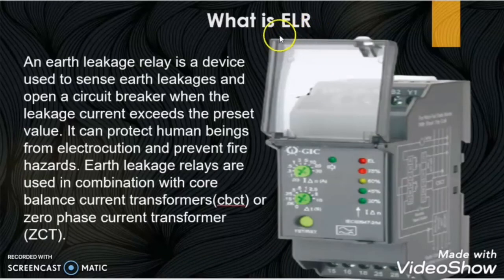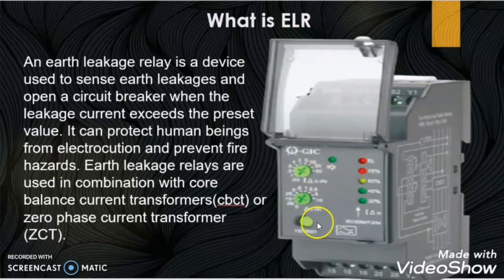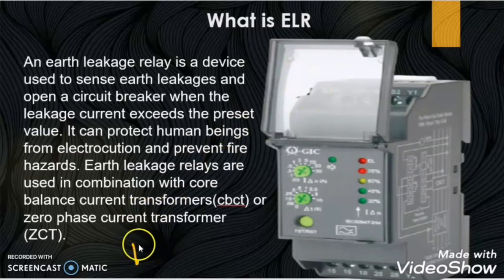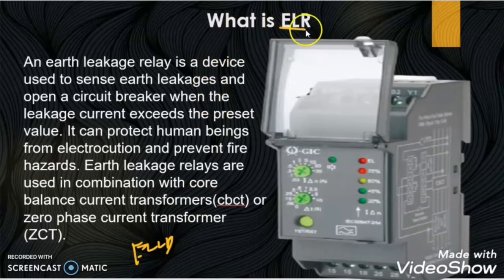Earth leakage relay is a sensing device which senses the earth leakage current. When the earth leakage relay finds this earth leakage current more than its preset value for more than its preset time, then the earth leakage relay opens the circuit breaker in order to break the circuit. The function of ELCB, that is earth leakage circuit breaker, and the function of ELR, that is earth leakage relay, is same but the operation is different.